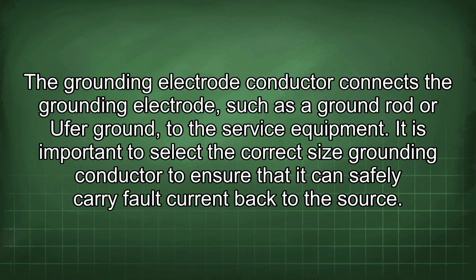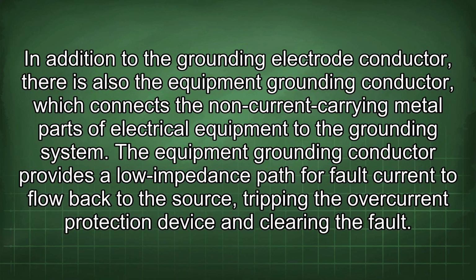It is important to select the correct size grounding conductor to ensure that it can safely carry fault current back to the source. In addition to the grounding electrode conductor, there is also the equipment grounding conductor, which connects the non-current carrying metal parts of electrical equipment to the grounding system. The equipment grounding conductor provides a low impedance path for fault current to flow back to the source, tripping the overcurrent protection device and clearing the fault.